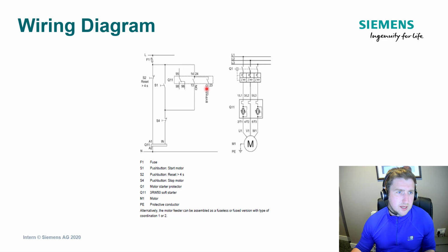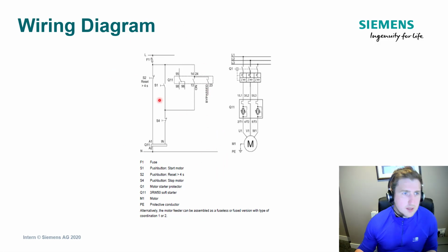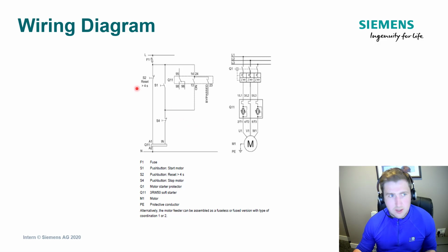Well, you can see here on this side you've got the control circuit layout. So typically you've got a start command, a stop command, and a reset command. So here you start and you stop connected to this in terminal here, and you've also got a reset command which is connected through from your A1 and your A2 terminals. So if there's a fault or a warning and the device stops, or perhaps there's been an overload, what you have to do is you have to acknowledge that, and you do that by pressing the reset button.